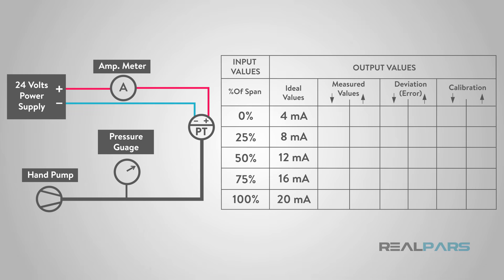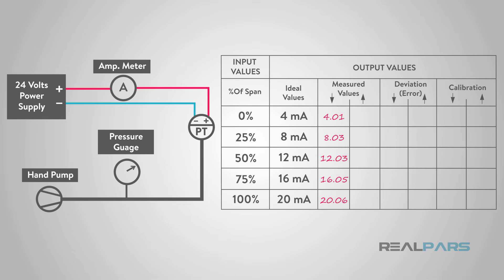To perform an as-found check, an accurate and precise instrument is used to develop process signals corresponding to 0%, 25%, 50%, 75%, and 100% of the process range of the transmitter. The corresponding transmitter output in milliamps is observed and recorded. This is called a 5-point check. Then, in order to check for hysteresis — a phenomenon whereby the sensor output for a process value is different going downscale as it is going upscale — the output signals corresponding to 100%, 75%, 50%, 25%, and 0% in order are recorded.